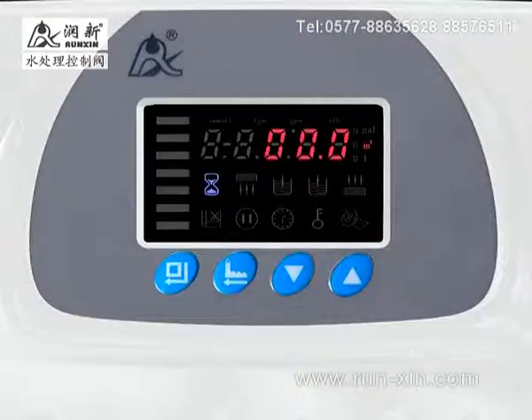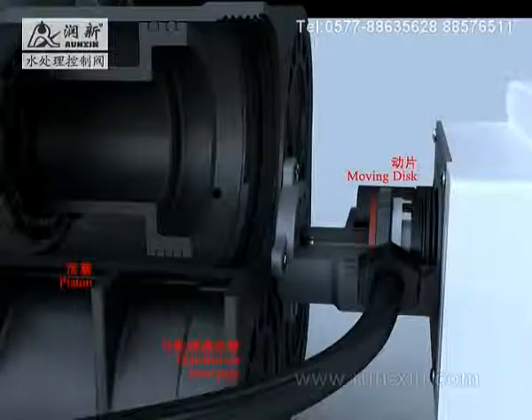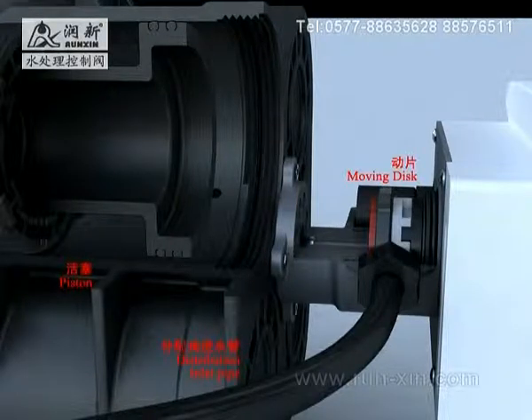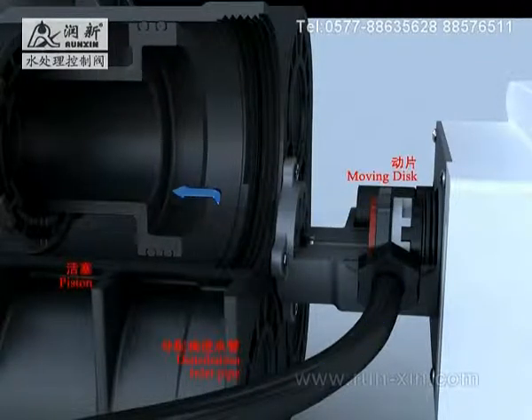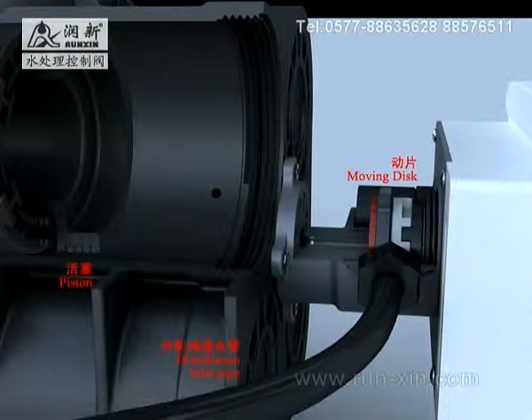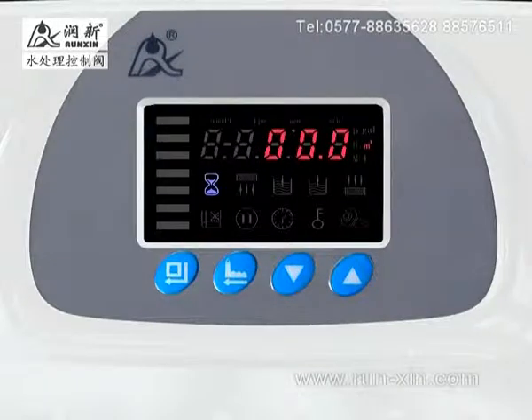When service flow rate reduces to 0, the system starts regeneration. The motor, controlled by the main control board, drives the big gear to rotate, and also drives the moving disc, which is fixed with the shaft. With the change of relative angles of the moving disc and fixed disc, the flow channels are changed. Small parts of raw water go into the distribution valve through 4 chambers and control pistons opening or closing to change its flow channels. When it arrives at backwash state, the symbol of backwash state lights.